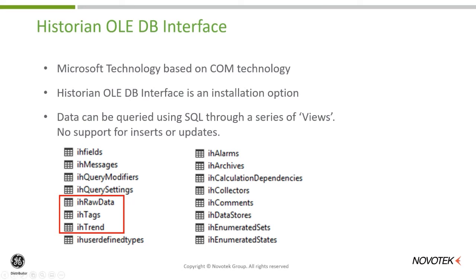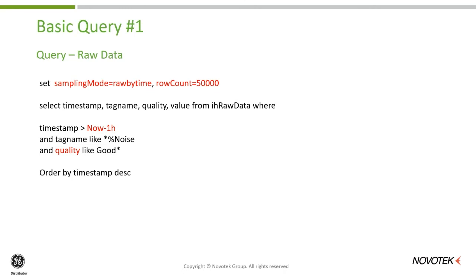Looking at a simple example — recovering raw data from historian. The query looks very much like an SQL query but with a few extra features. There's a concept called a sampling mode: in this case, I want raw data by time, not interpolated — the actual data points stored in historian. Alternatively, I could retrieve data by count, say the last 100 values. There's also a limit on the amount of data to bring back — here, no more than 50,000 rows.